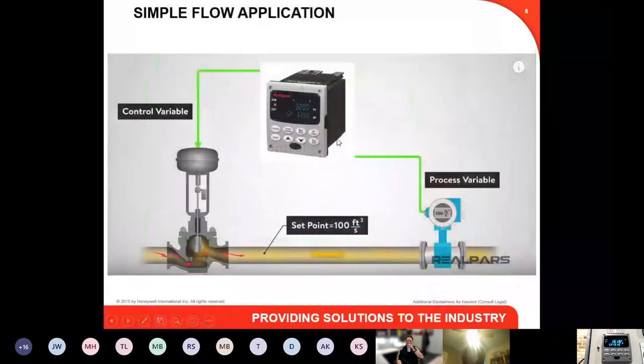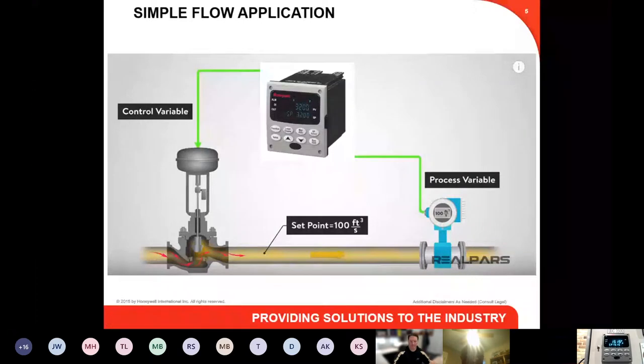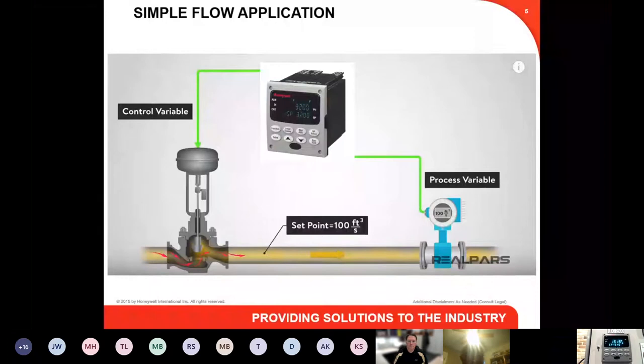Not only heat control, but you can also apply the UDC to flow control loops and level control loops — supplying a 4-20mA input from a transmitter measuring flow, then supplying a 4-20mA or on/off output to a process control valve to vary the flow.